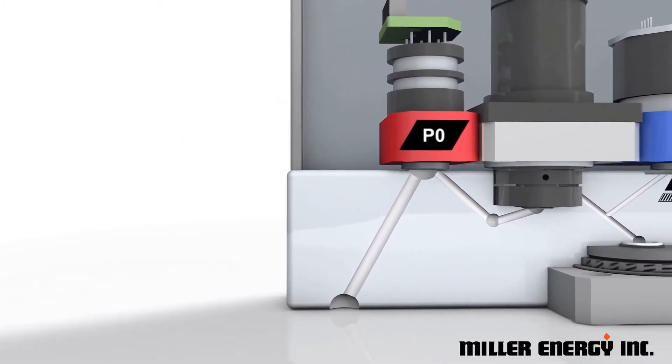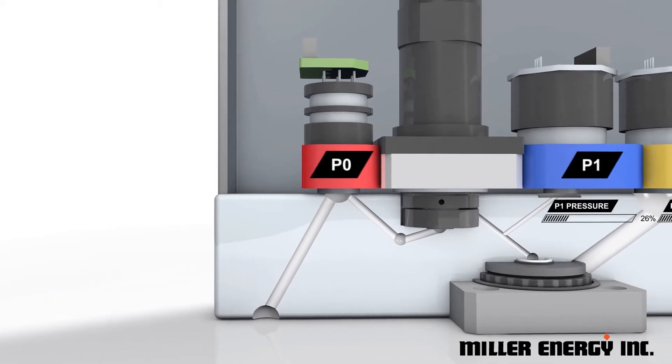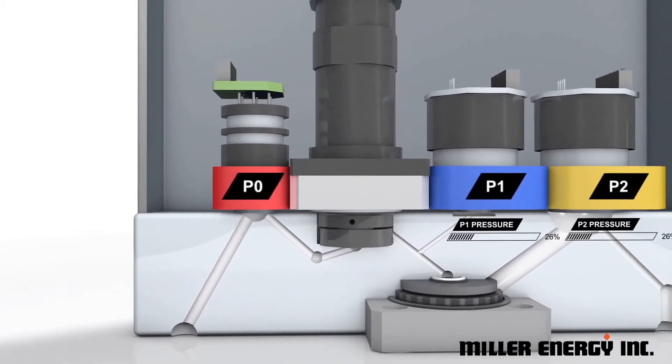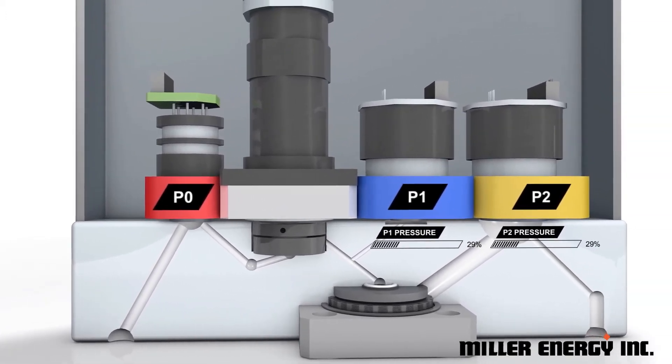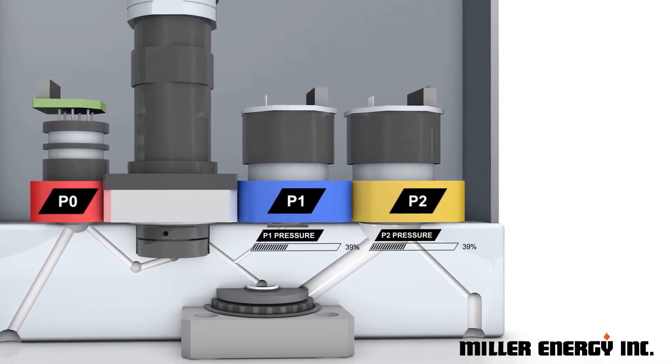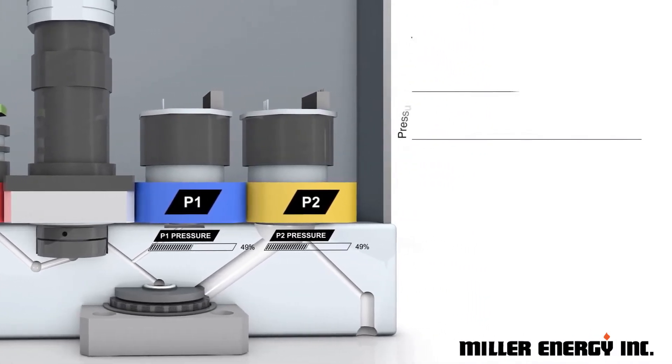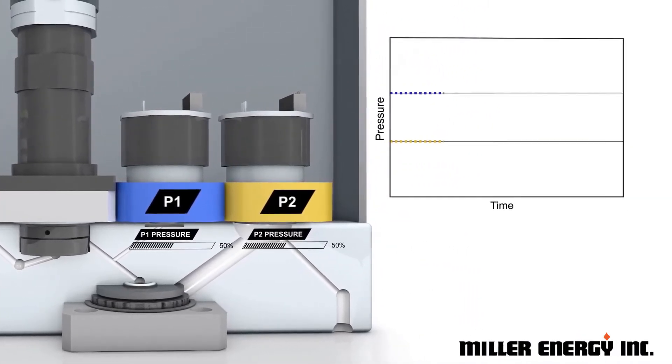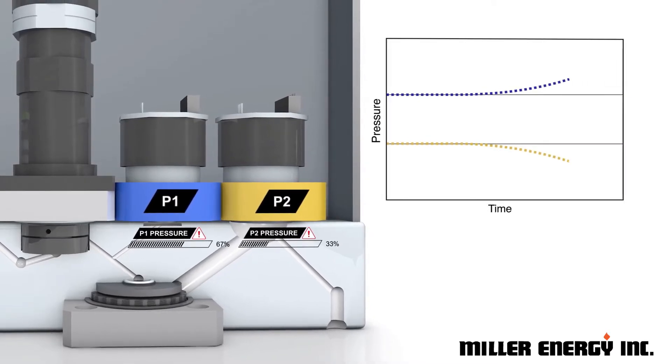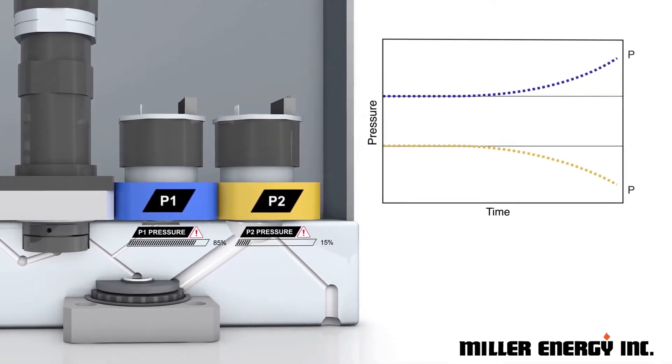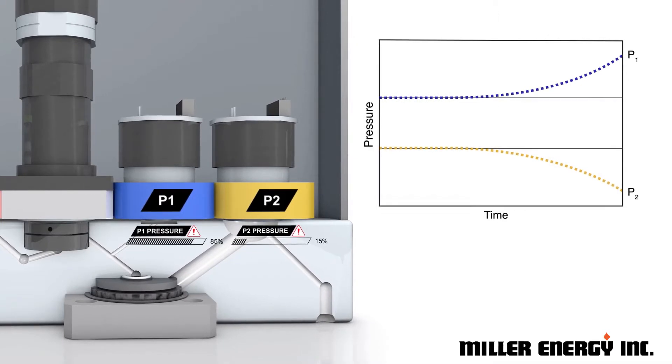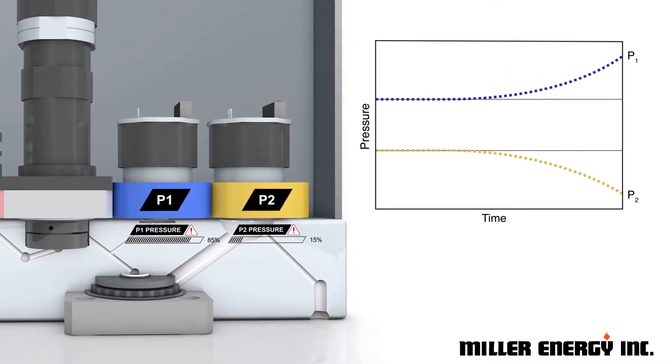This also means the two individual pressure transducers must be perfectly matched. By nature, all transducers exhibit some level of change over time. If they change by different amounts or in opposite directions, the product will become increasingly inaccurate as these offsets are squared in the mass flow rate calculation.